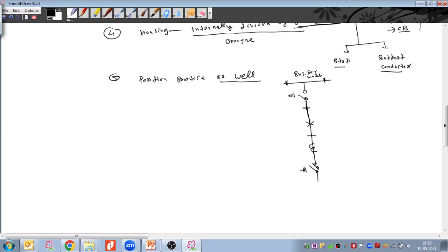And then this would be a separate compartment. Up to this we can make a separate compartment. And in case we are using the high line feeder, we have to use the line earthing switch. So this line earthing switch will also have a separate compartment. And in case we are using the VT, the VT will have a separate compartment, and then it will go to the termination equipment. We will discuss today what kind of termination equipment we take. So we discussed yesterday the partition practice of the GIS enclosure.